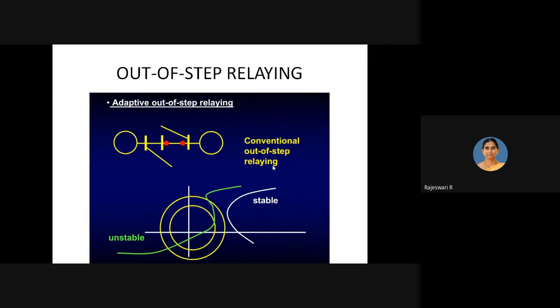This is performed with the help of two different functions, out of step tripping and out of step blocking. But out of step relaying should be able to distinguish a fault from a power swing, and stable from unstable power swing, right? If a fault is there, the corresponding relays will operate, whereas for a power swing due to the out of step condition prevailing in the system, that swing may be stable or unstable. So the relaying should be able to distinguish stable and unstable power swing.